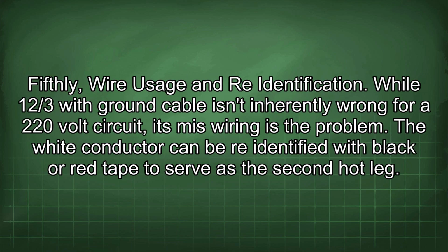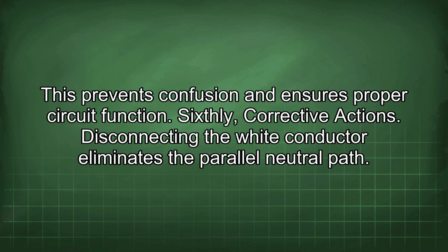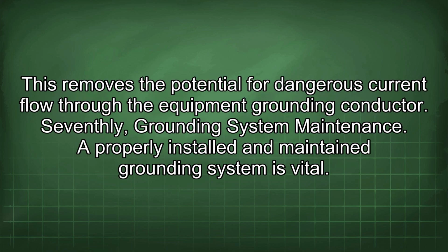Fifthly, wire usage and re-identification. While 12/3 with ground cable isn't inherently wrong for a 220-volt circuit, its miswiring is the problem. The white conductor can be re-identified with black or red tape to serve as the second hot leg. This prevents confusion and ensures proper circuit function. Sixthly, corrective actions. Disconnecting the white conductor eliminates the parallel neutral path. This removes the potential for dangerous current flow through the equipment grounding conductor.